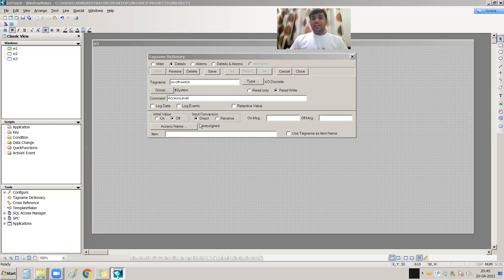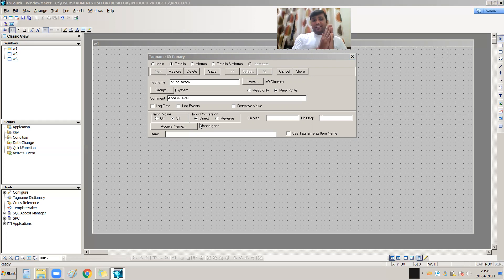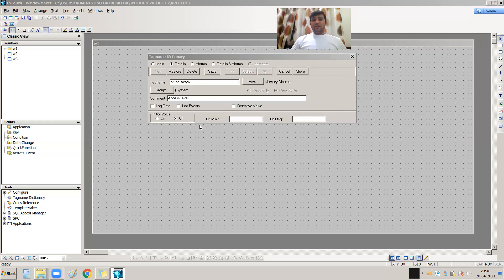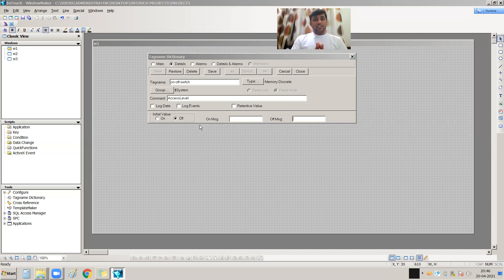IO Discrete means the tag has a connection with the PLC through an address. That address resides in the PLC. Since we are not discussing the addressing part right now, I am using internal tags of the SCADA. That's why I select Memory Discrete — it resides in the SCADA memory with no PLC relation. I have created the On-Off Switch tag, so save and close.